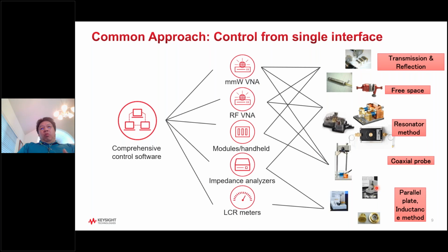So now, what do I do, or how can I make these material measurements? When it comes to material measurement, you need some sort of software. Perhaps you can do it yourself, because some of the formulas are in the public domain. What Keysight provides is comprehensive software that controls many instruments. The second part is the actual instrument: an RF instrument, LCR meter, or impedance analyzer. It depends on the measurement method as well as your frequency of interest, and many times also on the budget. The third part is the fixture. We have a variety of fixtures, depending again on which measurement method you choose, shown on the right side, and on your sample restrictions.